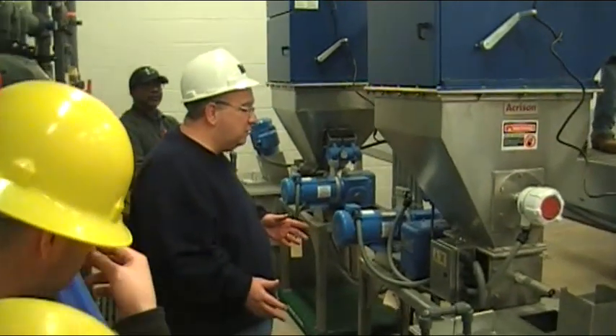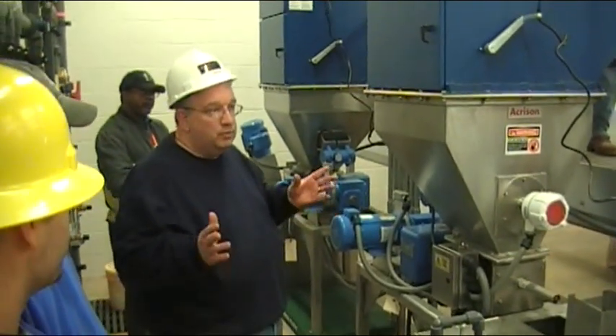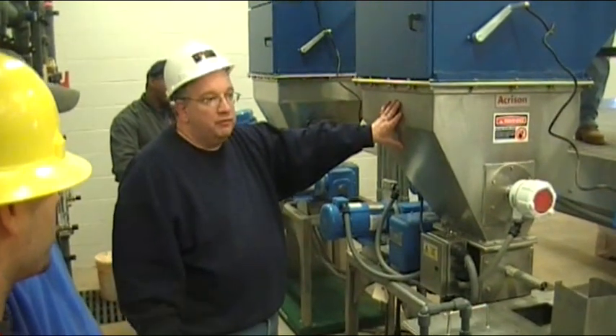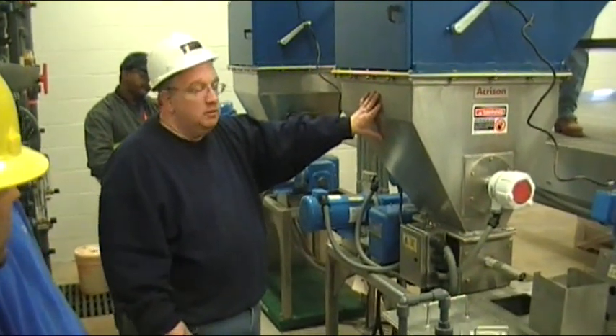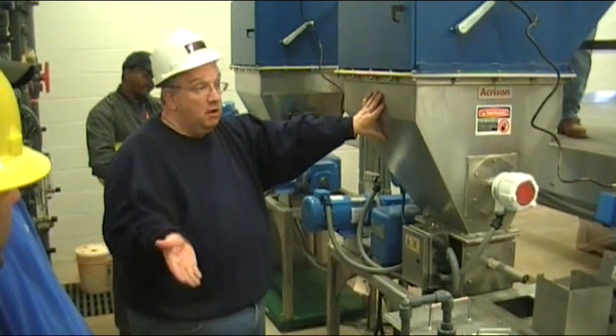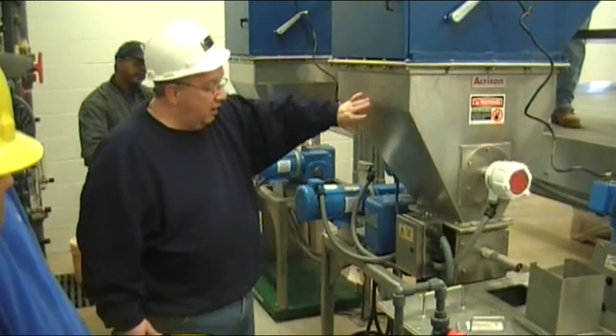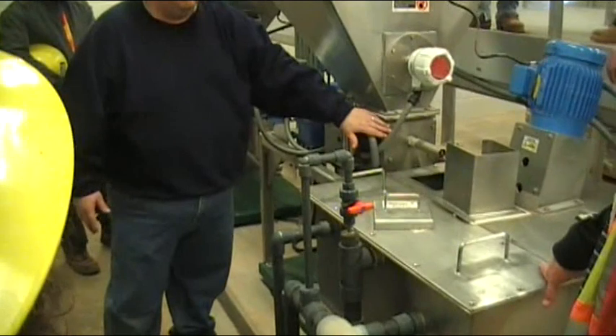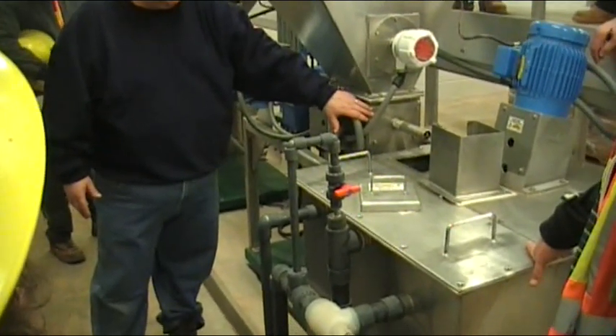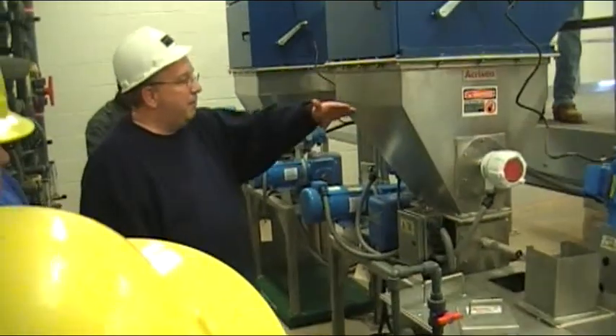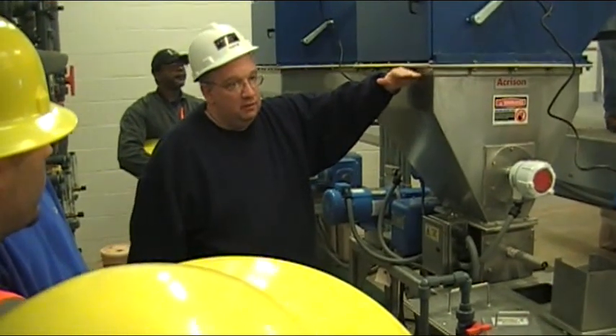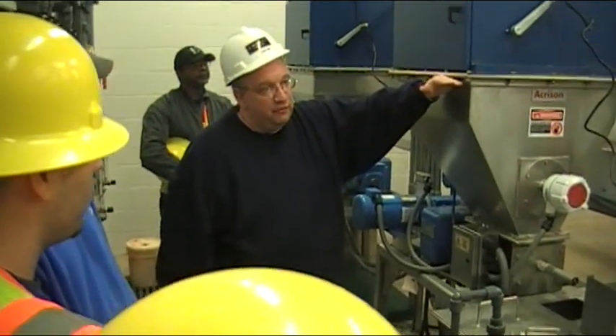Fluoride is approximately 75 to 80 pounds a cubic foot. This is a 4 cubic foot hopper, so that would be 80, 160, 320. And you could probably put another 80, maybe another 40 pounds in here. So 500 pounds would be right about here anyway, for the most part, about 450.